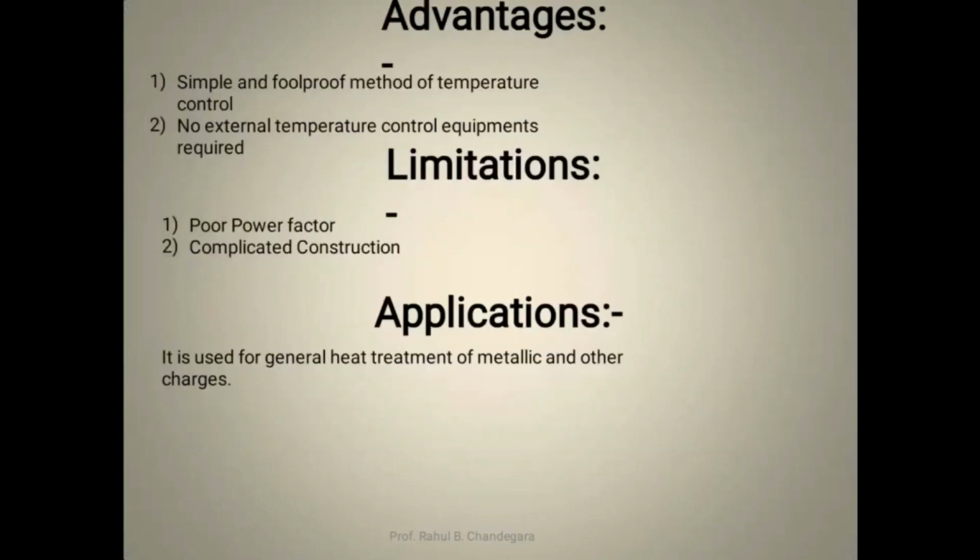Now the advantage of this method is a simple and foolproof method of temperature control. No external temperature control equipment is required. Limitations: poor power factor and complicated construction. The main application of this method is general heat treatment of metallic and other charges.